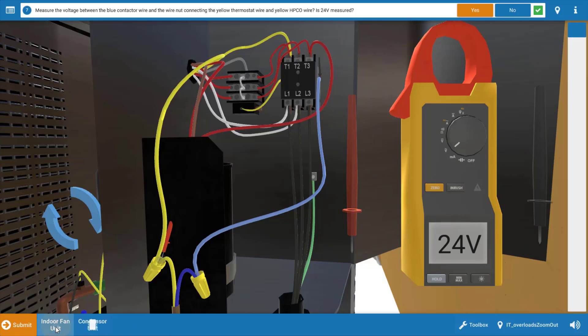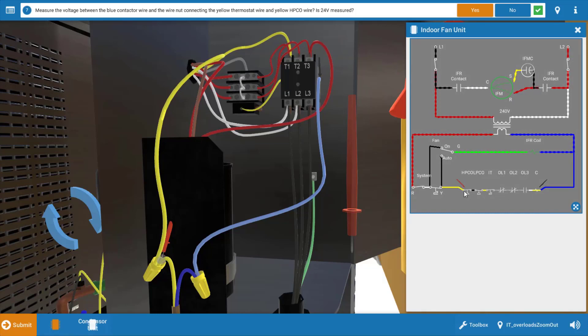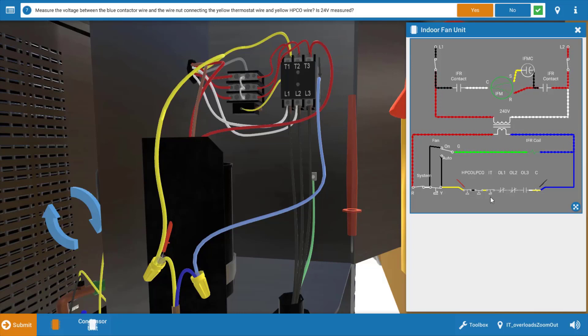Now again, let's take a look at the wiring diagram. You can see the placement of our leads. Our red lead is actually placed on the line feed to the low pressure cutout coming out of the thermostat. So again, we verified the thermostat contacts are closed.